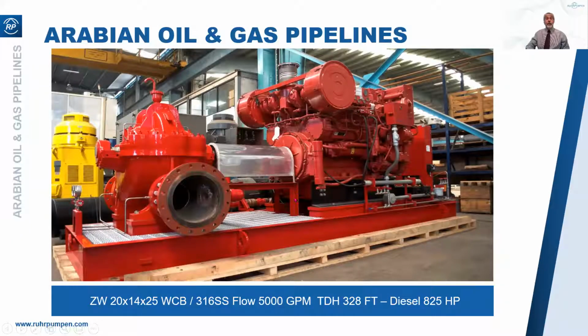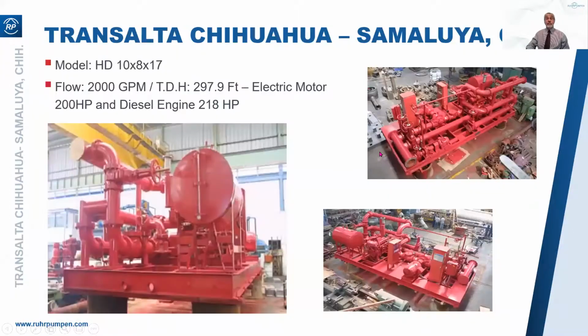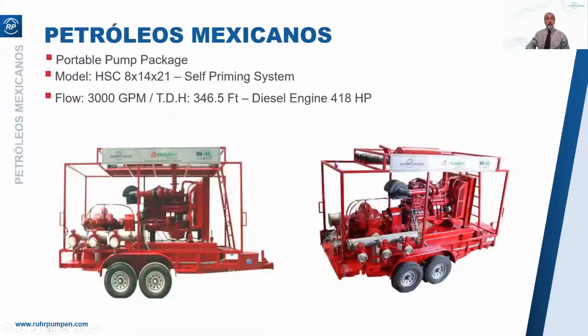Here we have a big pump. It's a 5,000 gallon a minute, and the diesel engine is 825 horsepower. So a big beast. Again, a big skid here with diesel and motor pumps on one big skid. There's a little sidebar here, a trailer mounted pump. Really neat little pump package. Obviously, it doesn't comply with NFPA-20. That's because it's a transportable package.